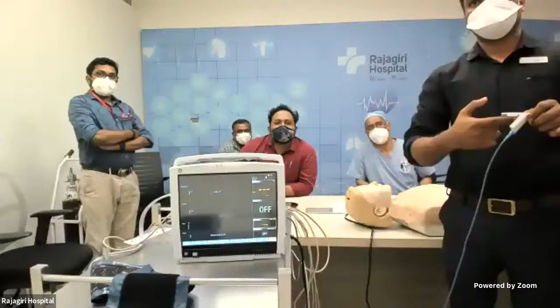Nadish, can you show it inside? The light should come on top, on your nail side, and it should not be directly over the nail, it should be pushed in, so it is passing through the nail. When you fix it properly, you will see a waveform on the machine. You have to wait; some machines take some time, but you will see a proper rhythmic waveform and a number that is more than 94 in a normal person. Once you see that, you can be sure the reading is right.